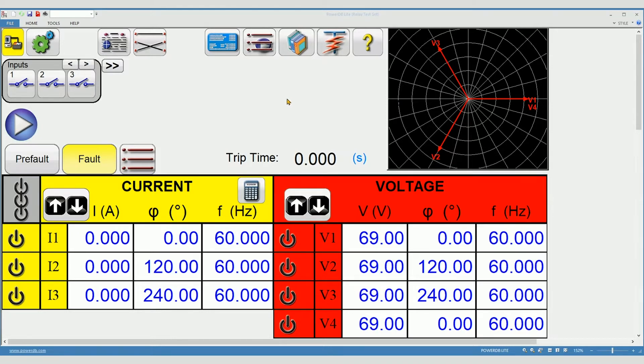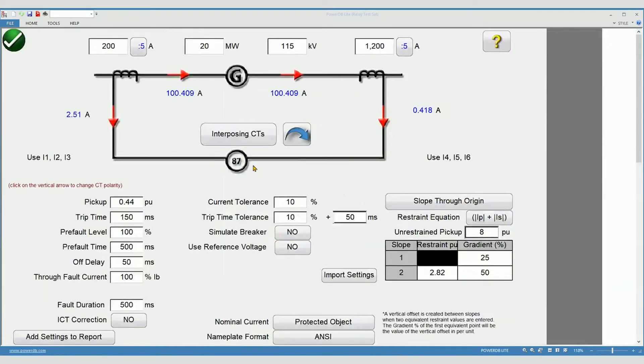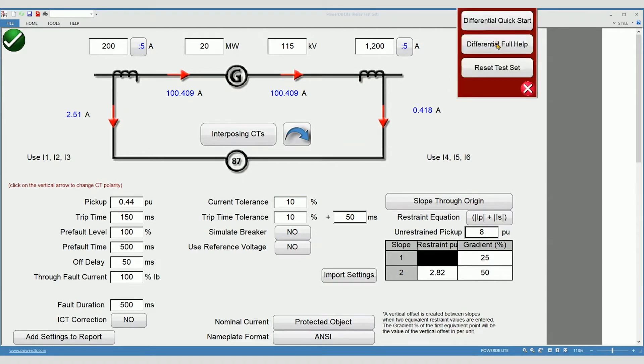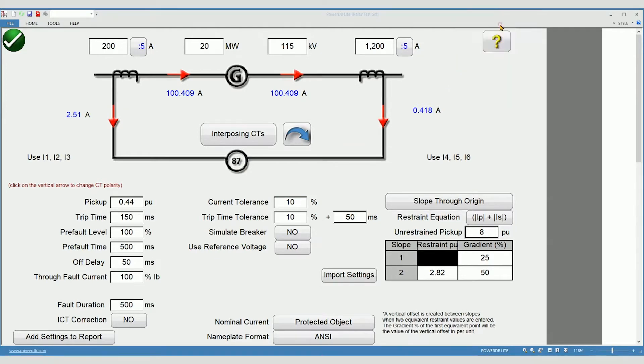Now, to get started, select the new test icon and then click on the generator differential button. The differential test feature includes specific help for testing differential relays. The differential quick start fully explains every setting on this page.